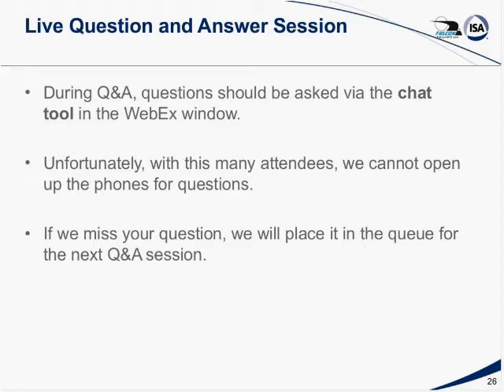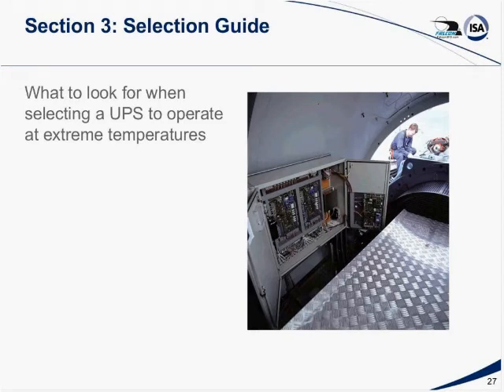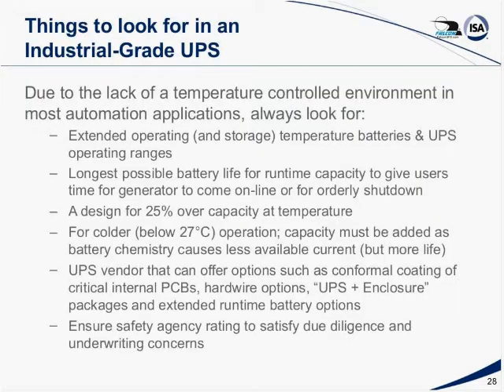Mike, could you go through a little bit for us the selection of an extreme temperature UPS? Yes. What are we going to look for when we select the UPS to operate at, well, not necessarily extreme temperatures, but in our SCADA applications, when I refer to extreme temperatures, I'm talking about anything other than 0 to 40 degrees C. When you go outside those ranges, as you will if you're outside almost anywhere in the world, we'll need to have a selection guide. So, since we don't have a temperature-controlled environment, you need to look for extended operating and storage temperature, both the batteries and the UPS operating ranges.